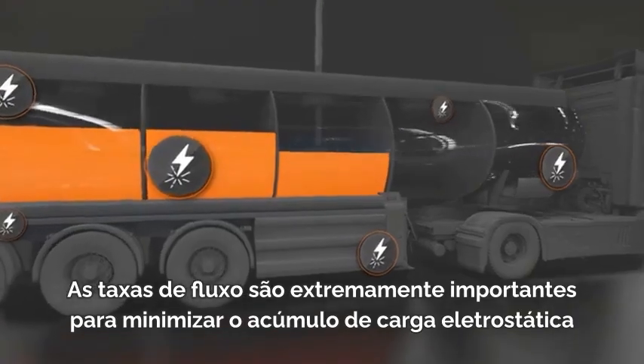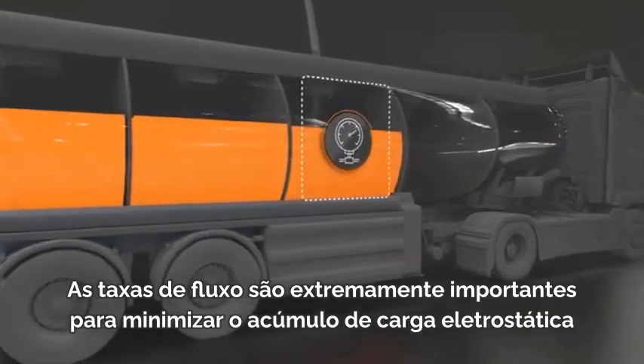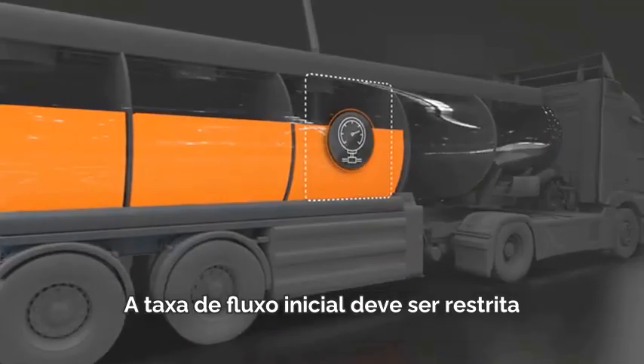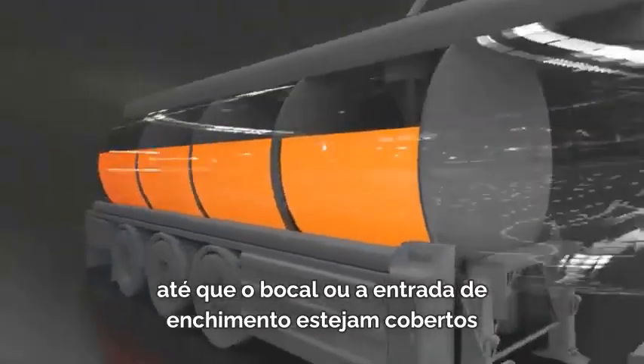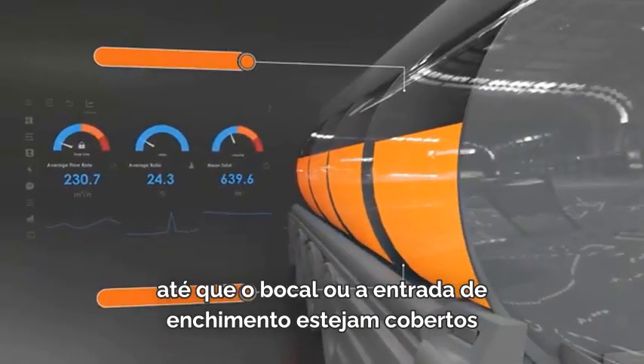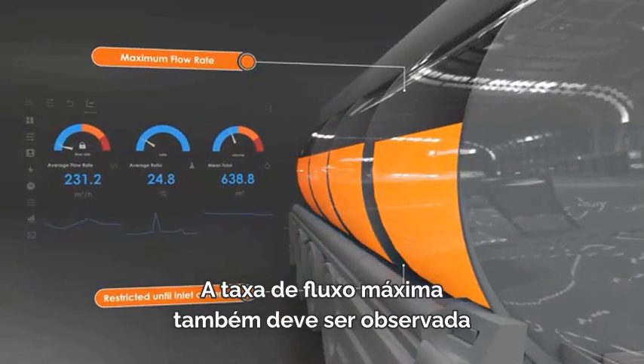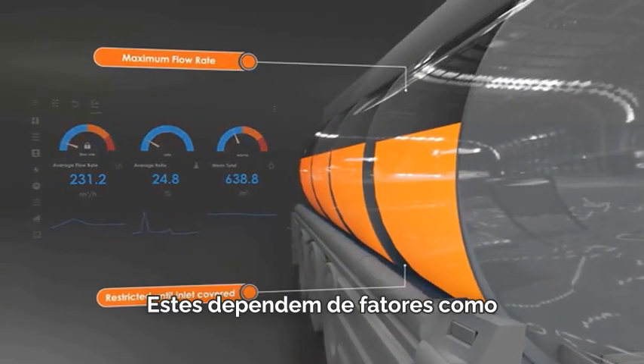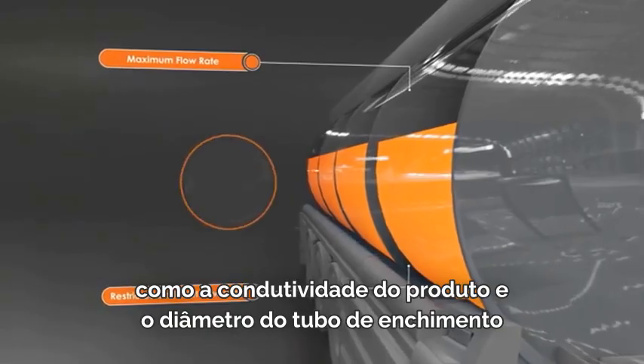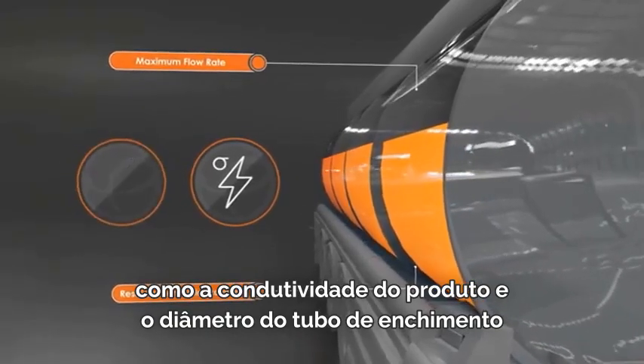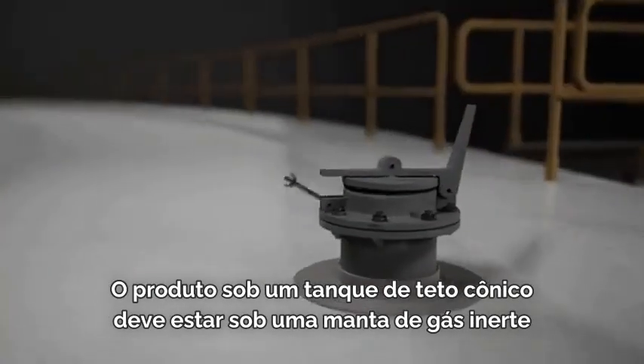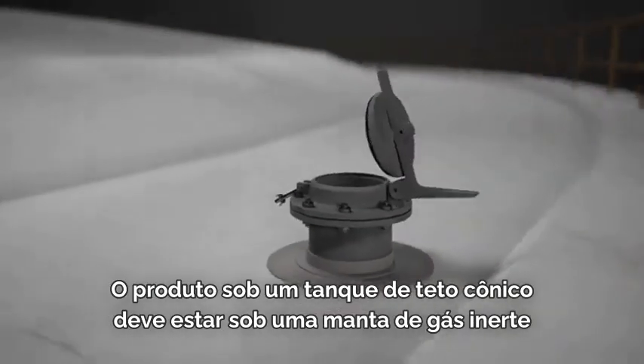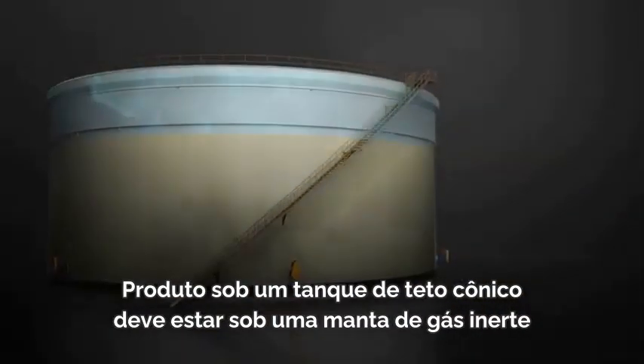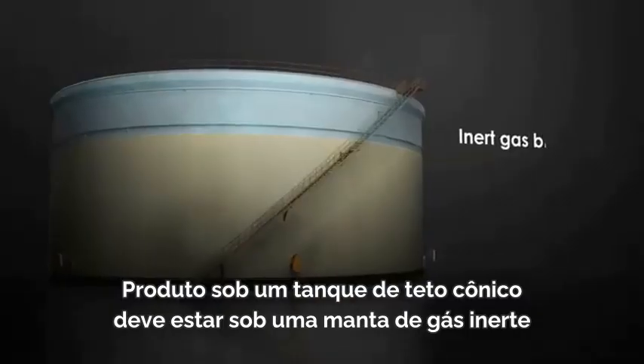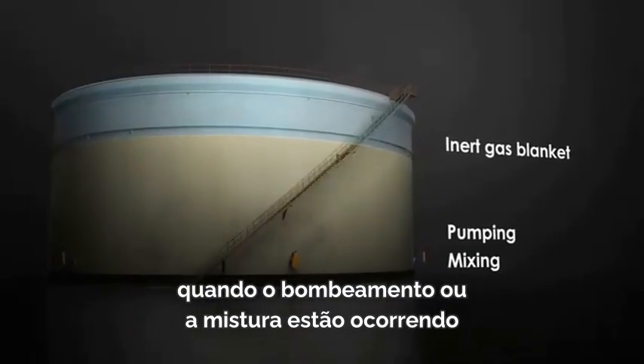Flow rates are extremely important in minimizing the buildup of electrostatic charge. Initial flow rate should be restricted until the filling nozzle or inlet has been covered. The maximum flow rate should also be observed. These are dependent on factors such as the conductivity of the product and the diameter of the fill pipe. We've already seen that gauging and sampling have the potential to induce a static discharge. Product under a coned roof tank must be under an inert gas blanket when pumping or mixing is taking place.